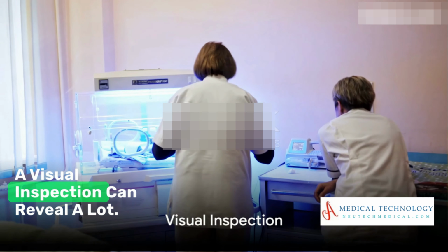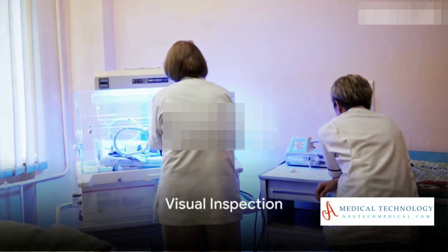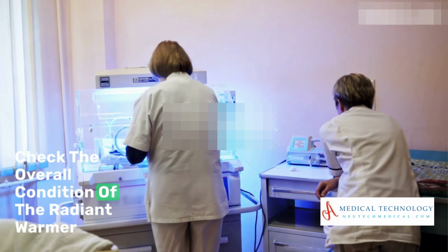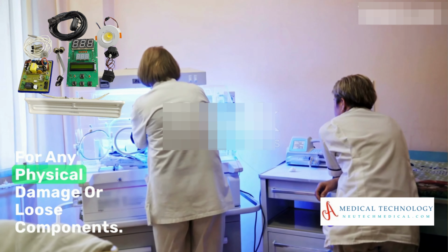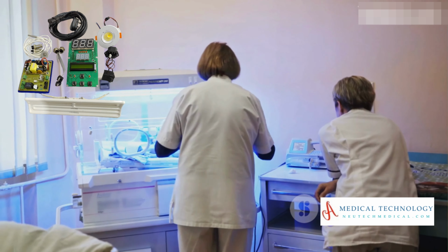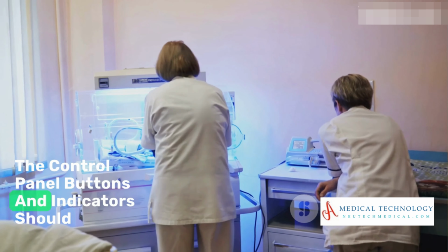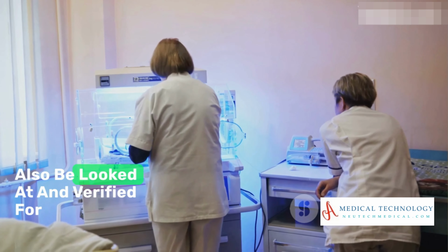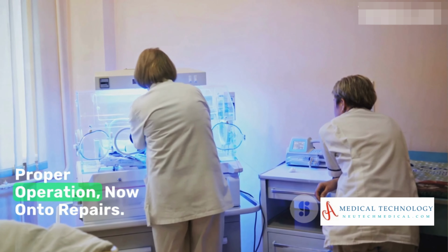A visual inspection can reveal a lot. Check the overall condition of the radiant warmer for any physical damage or loose components. The control panel buttons and indicators should also be looked at and verified for proper operation.